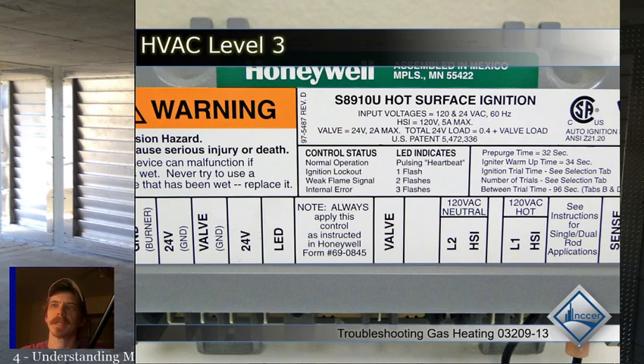And some equipment, instead of powering the reversing valve, will remove power from the reversing valve, because some systems are set up for the reversing valve to be normally in heating, which is most of them, but some systems are set for the reversing valve to be normally in cooling, which is a small few of them. I think mainly just Rheem these days, but there could still be a couple manufacturers that use a B terminal instead of an O terminal. An O terminal is the most common one, where the reversing valve, if it's energized, moves into cooling. If it's got a B set up, then that would be the reversing valve energized in heating.